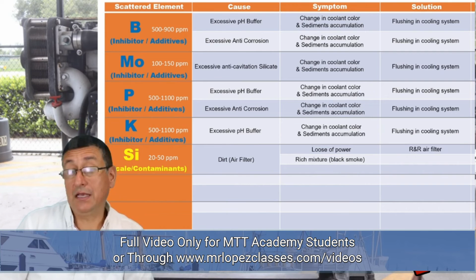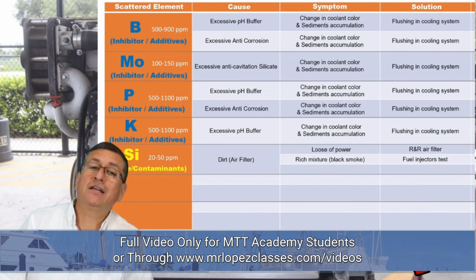In that case, due to the excessive amount of fuel, the color of the smoke is black, and you need to check the injectors. You need to remove the injectors and send them to the machine shop to test the pressure and spray pattern of each injector.